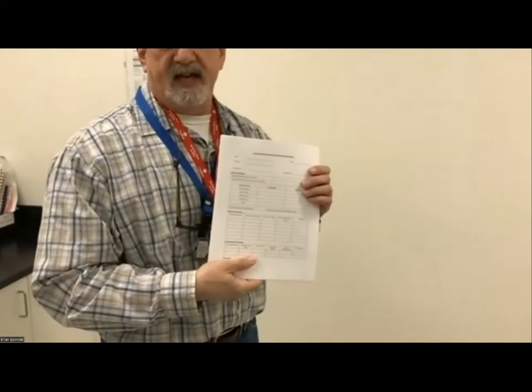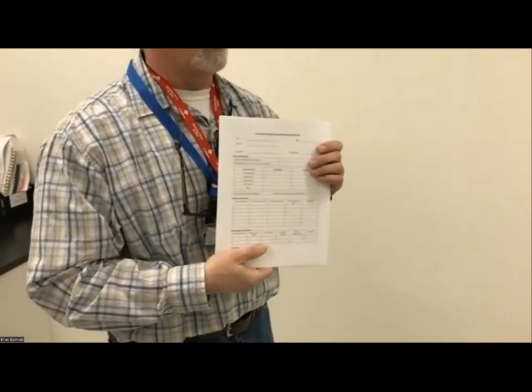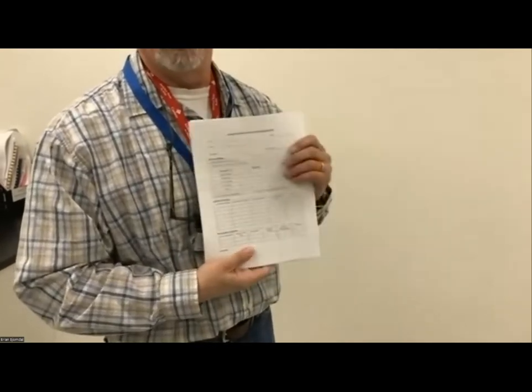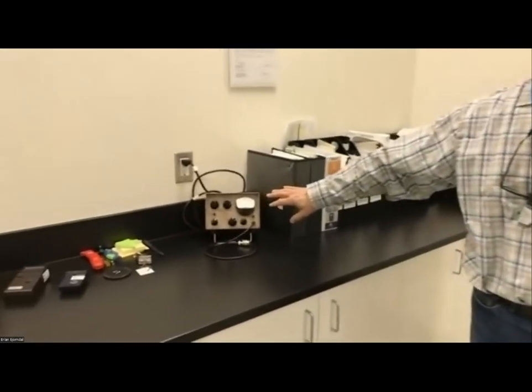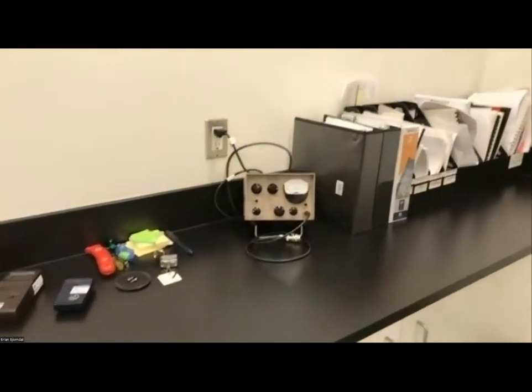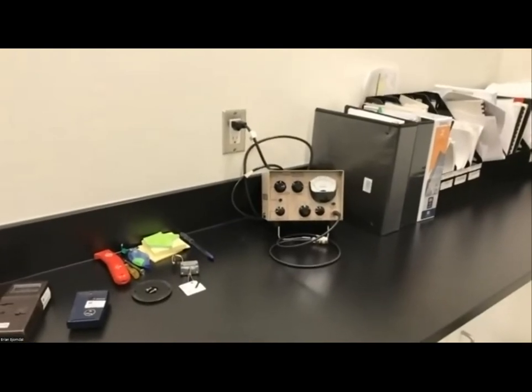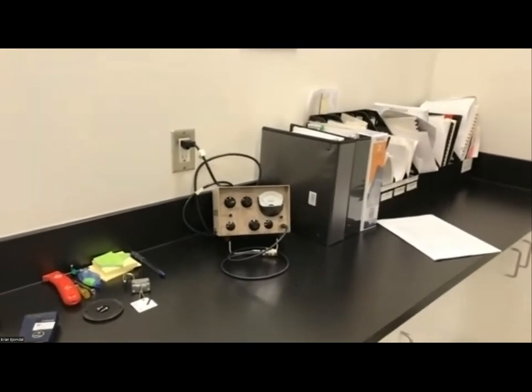So we'll get you to fill out any information and send that to us. Then we'll do a visual inspection and start a documentation trail on this instrument, including particular information and inspection information. When it's ready to go, if it seems like it's working, we will bring it in here and start to do a calibration. If your instrument has a scaler function, we do a pulser check of the system to make sure it's counting properly. Then it will go over here to the lab, to the instrument calibrator for exposure.